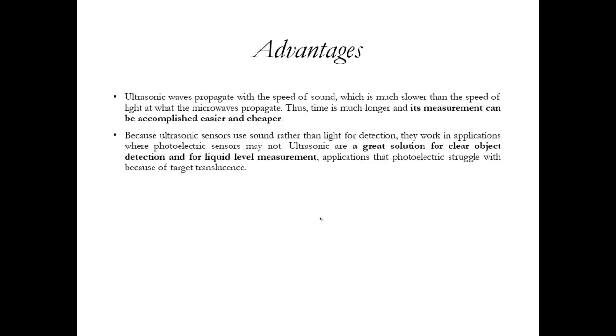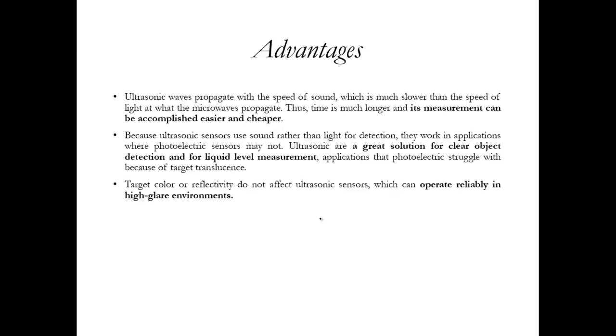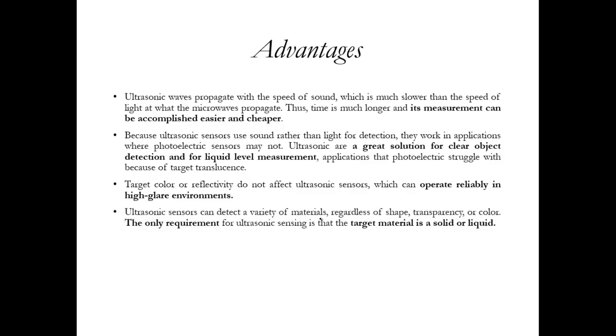But when we have clear object detection or liquid level measurements, where photoelectric sensors actually do not work, ultrasonic sensors are quite handy. In this case, target color or reflectivity will not matter, because they can operate reliably in high glare environments also. Ultrasonic sensors detect a large variety of materials, regardless of their shape, transparency or color. The only requirement is that the material should be solid or liquid.